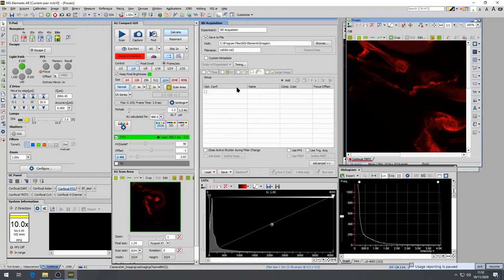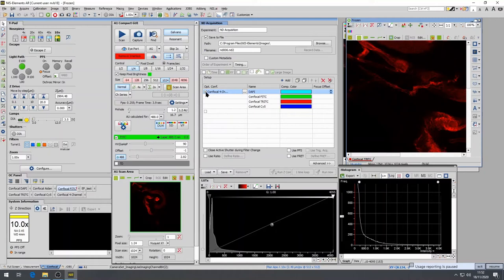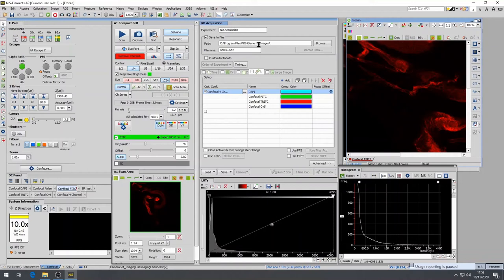So first, I'll show you the lambda. Within the lambda tab, which is in the acquisition tab, it is possible to define and use multiple optical configurations. At least one optical configuration must be identified in the lambda tab that is activated. So using this tab will ensure that the multi-dimensional acquisition uses the channel settings that you already predefined. The path up here represents the location that your file will be saved to.